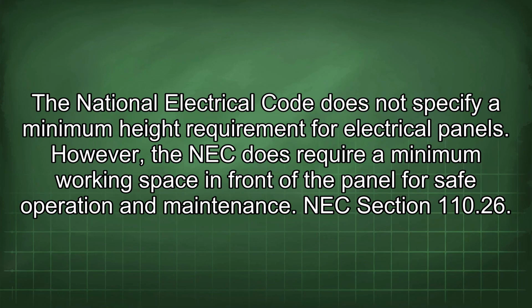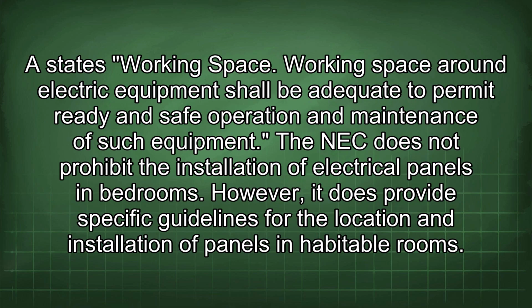The National Electrical Code does not specify a minimum height requirement for electrical panels. However, the NEC does require a minimum working space in front of the panel for safe operation and maintenance.